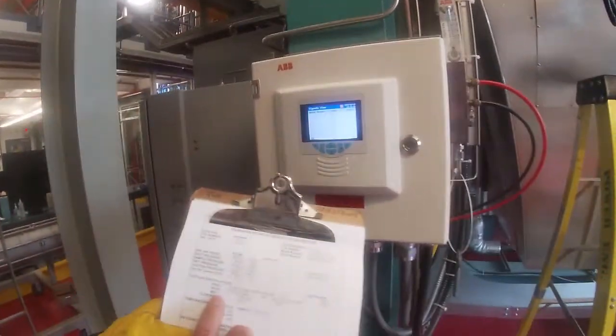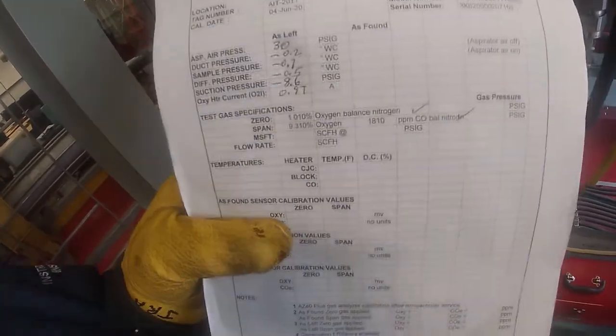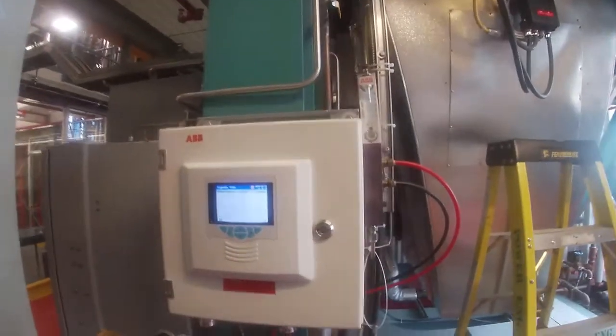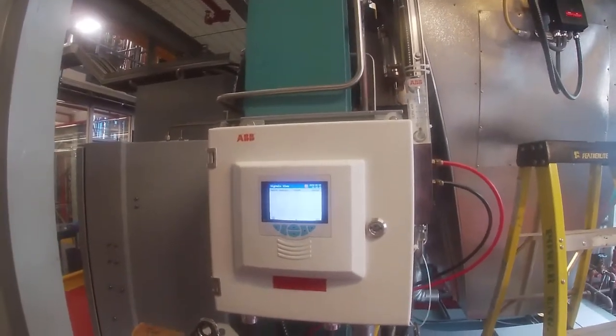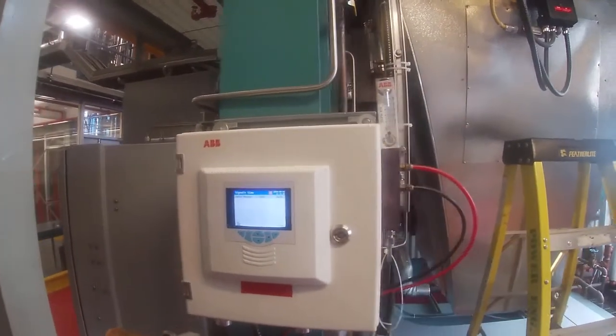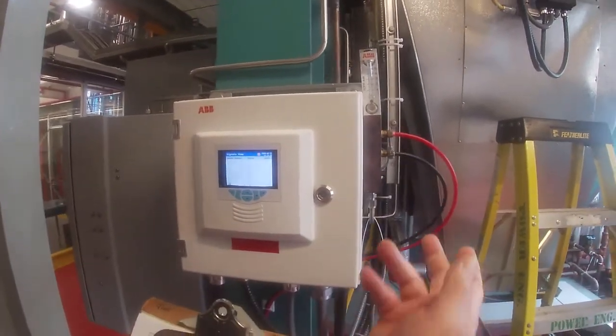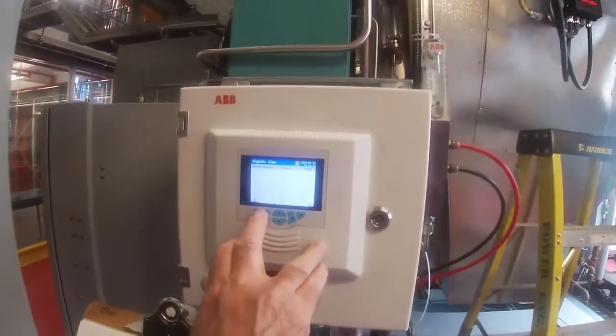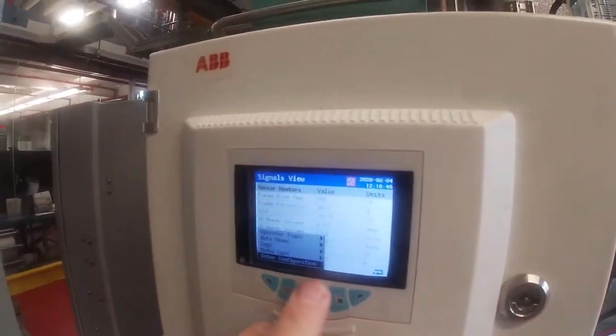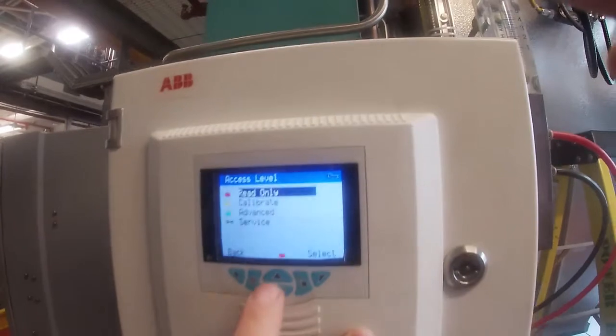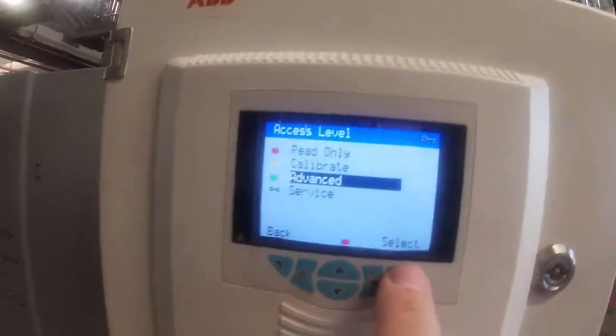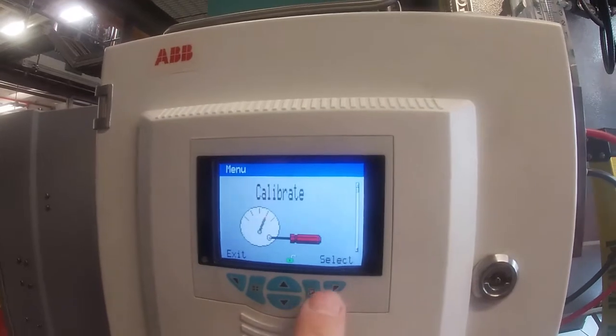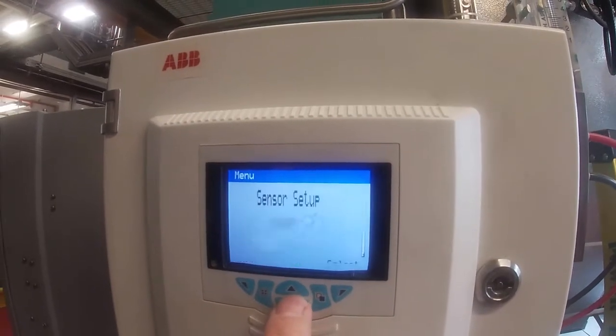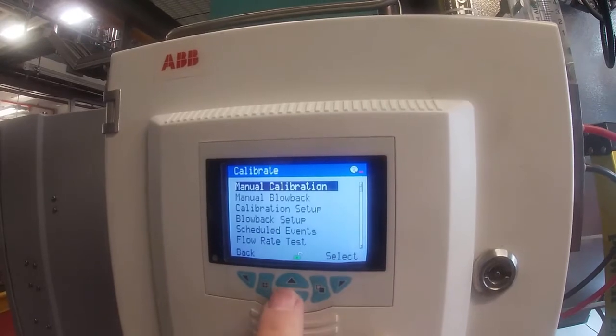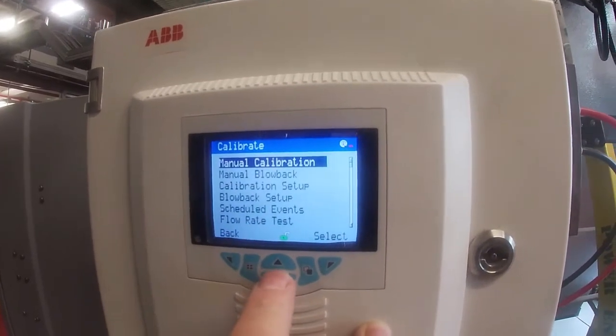Now, I also need to know something called a minimum flow sample test. So we've got to figure out where there is enough sample gas going in to overcome the gas that's being extracted out by the air aspirator. To do that, I'm going to go back to configuration and advanced, and I'm going to select it, and then go down to the flow rate test, bottom of the list there.